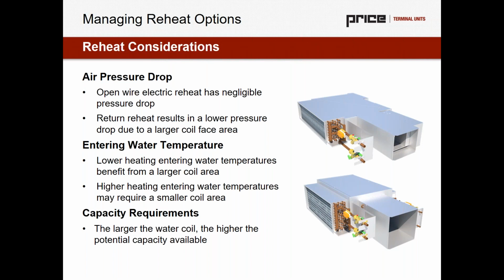Another thing that is noteworthy as well, and is especially important for you guys with that deadband requirement of 0.12 watts per CFM, is if we load up a piece of equipment with more air pressure drop, that's going to start to also drive up that watts per CFM operation, because a motor runs with higher watts as there's more external static pressure. So providing more of a low air pressure drop solution, such as a return reheat coil or an electric reheat option that has really negligible pressure drop, could be what's required in order to meet high CFM intended deadband operation, just because of that watts per CFM requirement.